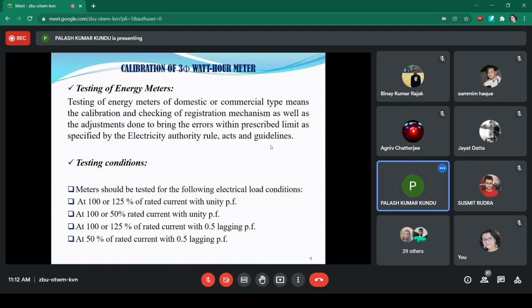to check the calibration and the registration mechanism, that means the dial rotation. So there are two types of error that generally occur in a watt hour meter. One is the error caused by the disc rotation due to a mechanical problem, because the disc will rotate according to the driving torque generated, and when the disc achieves steady speed, because there is a brake magnet or braking system, with the help of the braking torque the disc will rotate with a constant or uniform speed depending on the energy consumption.